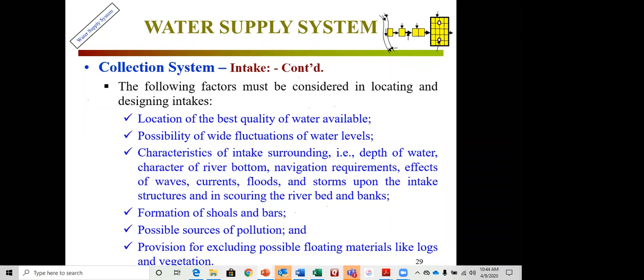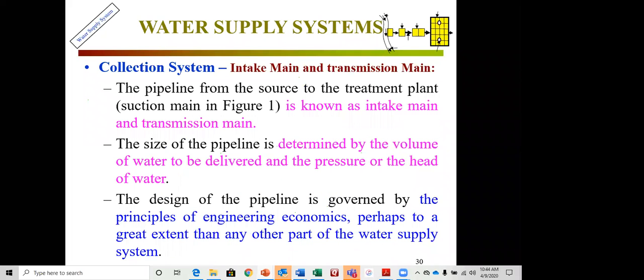Factors to consider for collection system siting include: location of best available water quality; wide fluctuation of water levels; characteristics of intake surroundings such as current, shifting bars; possible pollution sources downstream; provision to exclude floating materials like logs and vegetation. The pipeline from source to treatment plant — the intake main or transmission main — is sized using Q = AV. Pipeline design is governed by engineering economics, which drives cost considerations from a business and technical standpoint.